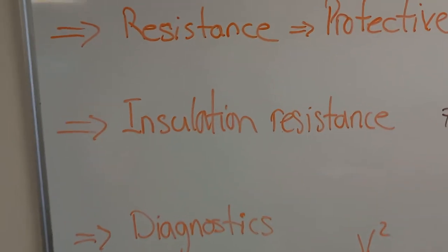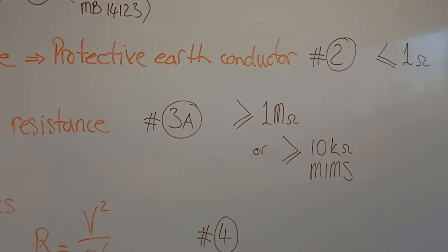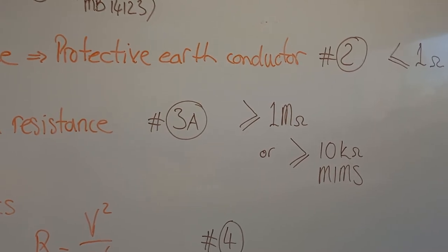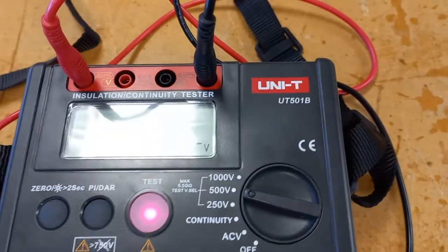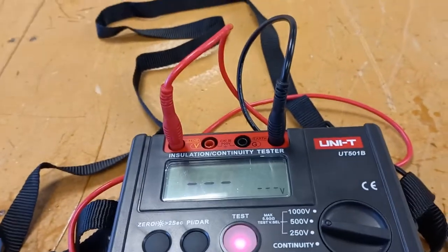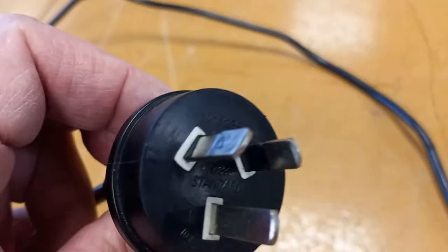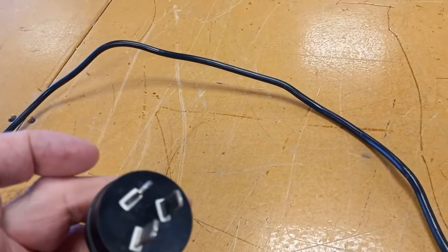The next test is the insulation resistance test. For this particular appliance, because it's not an MIMS element, the minimum insulation resistance is 1 megaohm. This is done using the insulation resistance tester at 500 volts DC, because we're measuring the resistance of the insulation. That is done by connecting the phase and neutral together at the plug, and then to earth.